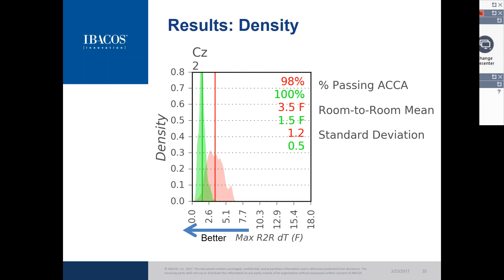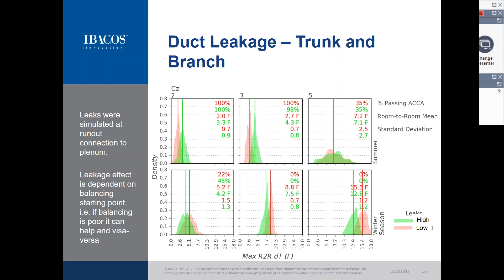I'll quickly go through some of the parameters to show their effects. We looked at duct leakage, simulating leakage at the takeoff from the plenum of the traditional system to look at its impact on uniformity. It had a fairly significant impact on the results between the red and green models. In some cases it helped, in some cases it hurt, depending on the starting condition of the tight duct system.